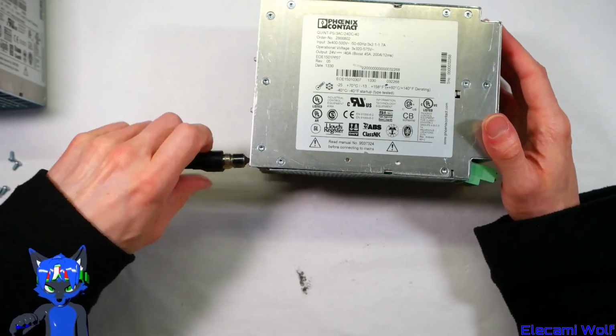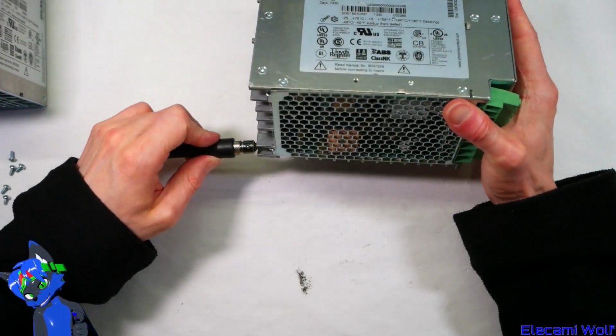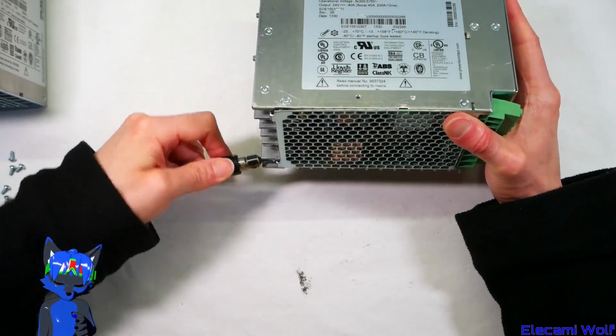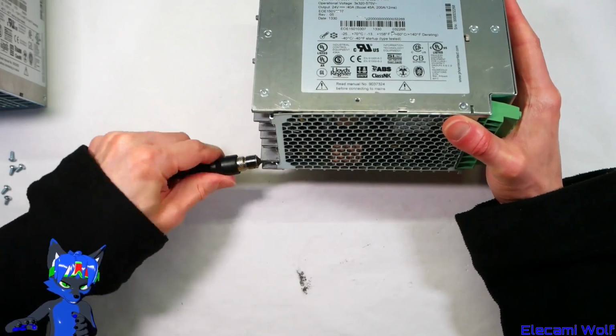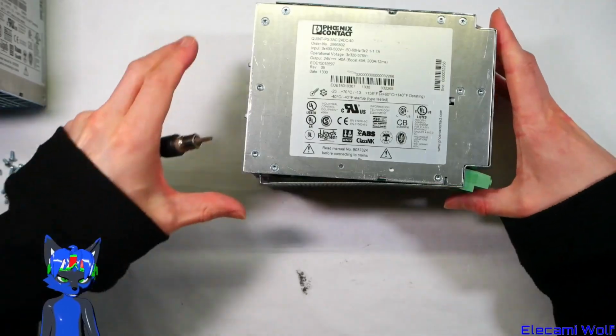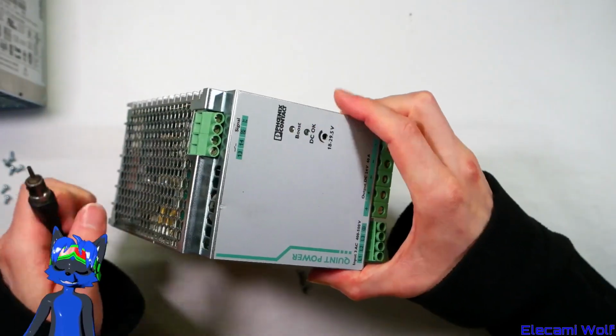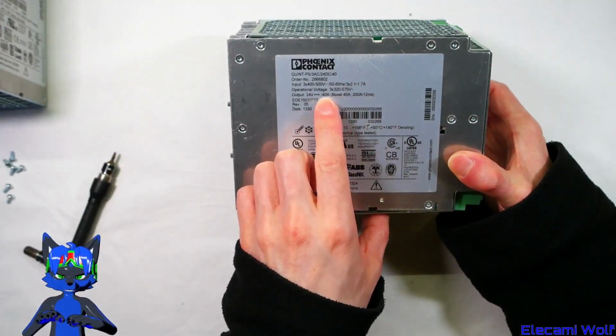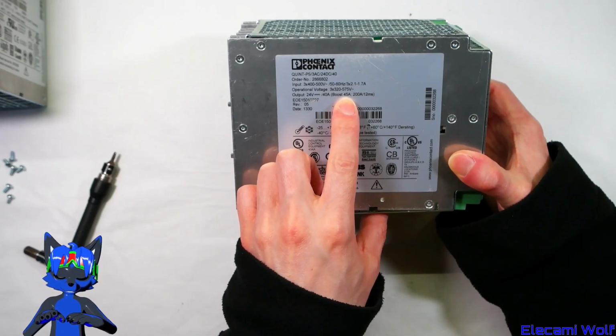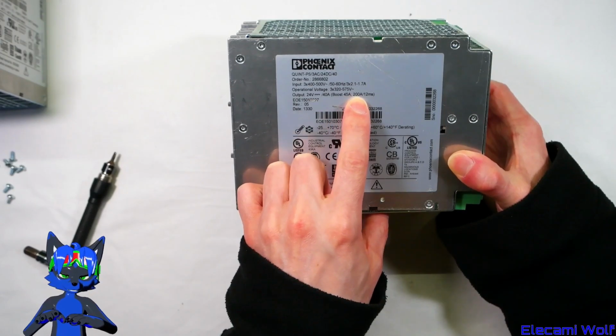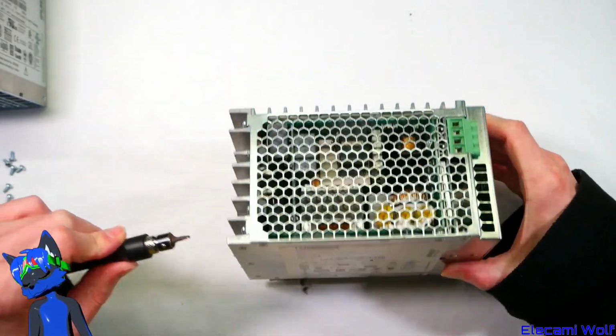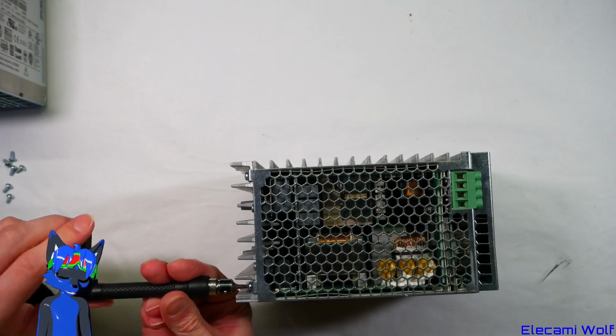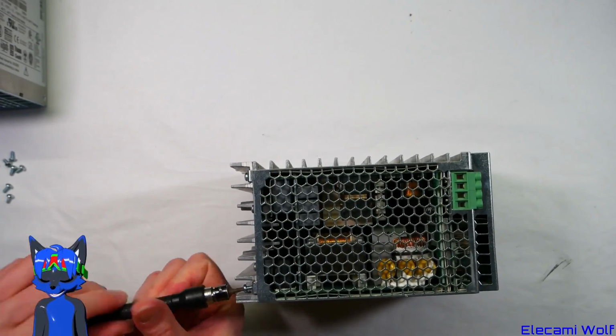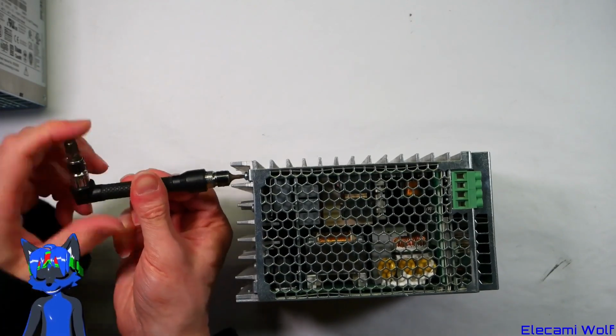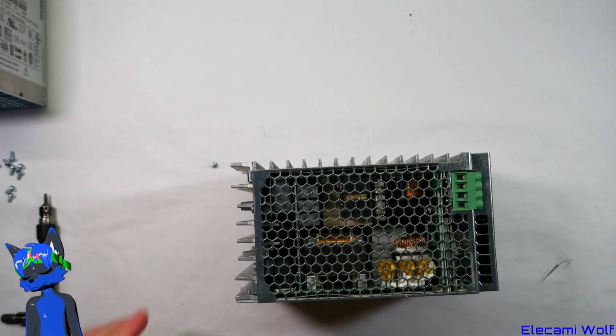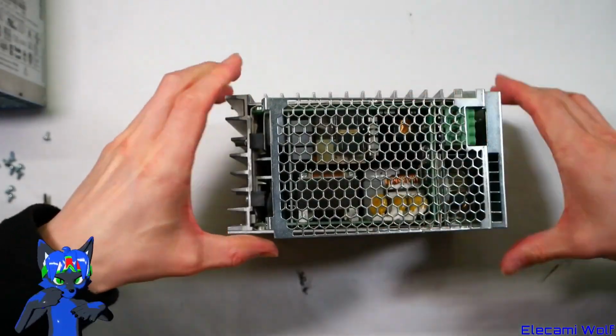You need to have some careful circuit protection if you're powering a whole bunch of stuff from this size of power supply. Need to properly distribute the power and use individual circuit breakers or fuses to get a sensible fault capacity before it enters small equipment, because this has the boost mode on it like what we saw before. It says 40 amps nominal, can boost to 45 amps which I presume is continuous, and can boost to 200 amps for 12 milliseconds for fuse-blowing capability, so it can deliver enough fault current to clear circuit protection without shutting down. Because if you're powering a lot of stuff off this, you don't really want it just shutting down when one thing gives up, or one little thing gets accidentally shorted out with someone's careless screwdriver.